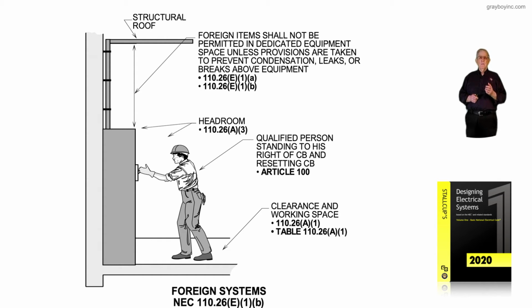And this Article 100 for switching ties into NFPA 70E, which says if the breakers have been maintained in accordance with NFPA 70B, Chapter 17, and then notice 70E 200.1, the informational note, recommends the use of 70B for maintenance procedures and interval checks and repair and switching and that kind of thing.